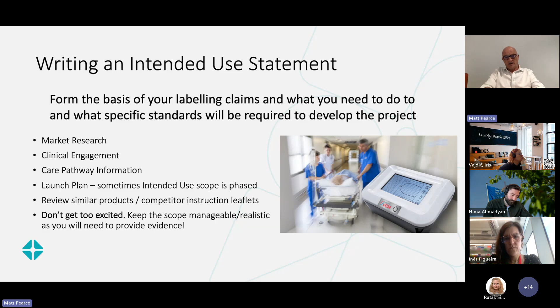Once you've written the intended use statement, you then need to create what they call a design inputs document, and all of this design intent is very important. So for all projects, at the beginning, ideally you want to list all of the design specifications that you are going to meet for this product, and in order for it to satisfy its intent, safe and effective use in the intended use setting. So this might cover areas of robustness, cost.